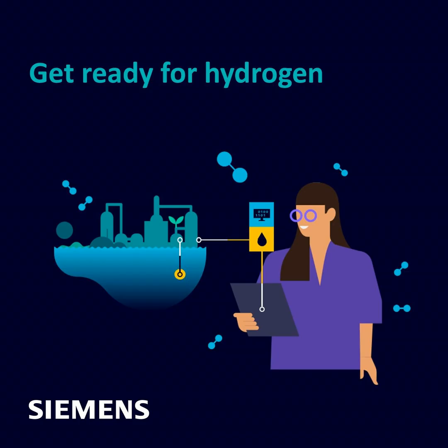Why? Because these are data, information that come, for example, from the digital twin of the plant, in other words, from our engineering model where I have all the plant data. On the other hand, I have the information that comes from the process values, which originate from the control technology. And as the third pillar, so to speak, the information that comes from the simulation, that is the simulations that we also continue to run in operation, and where we make comparisons between simulated data and the real data, from which we derive insights.